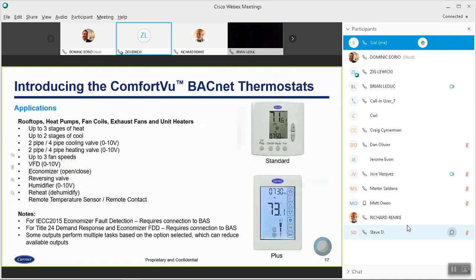So, the applications that you can use with this, basically 3 stages of heating, 2 stages of cooling, 2-pipe, 4-pipe type of cooling and heating valves. And this is where you can use your 0 to 10 output. You could have multiple fan speeds. You can control VFD, economizer, all the stuff that you see here.